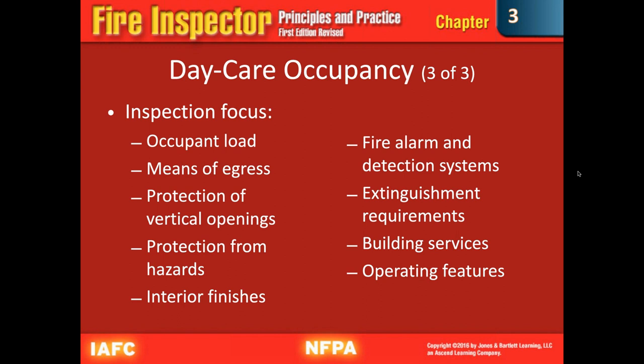discharge from the exits. Where do they go when they get out? Are they going to dump out immediately into a street and get run over? Or is there a fire hydrant sitting right outside the door that's going to block people, that kind of thing. Proper illumination of means of egress and emergency lighting, clear marking of means, and any special means of egress features. Protection of vertical openings, protection from hazards, interior finishes, fire alarm and detection systems, alarm and communication systems, extinguishment requirements, building services and operating features.